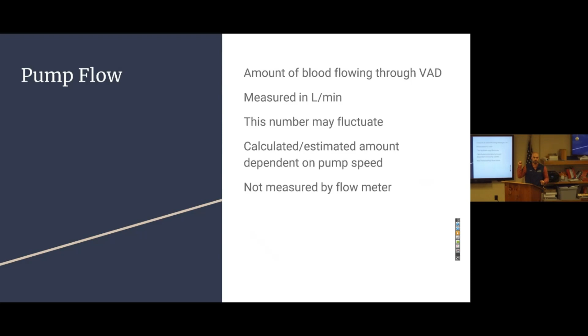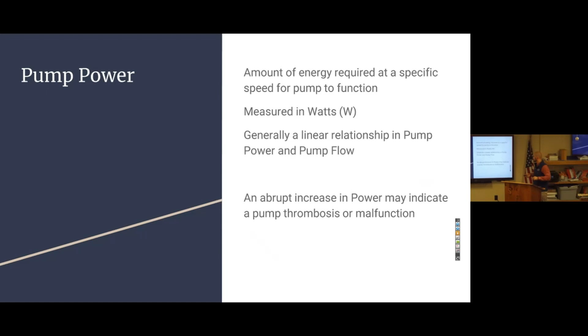Pump power. So this is how much work the pump is doing to get things going, okay? It's the amount of energy that's required at that pump speed to function that well. It's measured in watts. And generally there's a linear relationship that the more flow I have, the more power I'm going to require to have that flow, right? That kind of makes sense, right? If you have this sudden increase in power, that could potentially mean that we have something blocking that pump that I'm now having to work harder. We think about pump thrombosis, and we're going to kind of talk about complications, but this is a very common occurrence. That's why I wanted to bring it up a little early. Or there's another malfunction of the VAD.